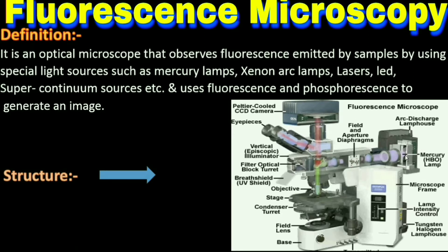The light source should be a mercury lamp or xenon arc lamp. Here we are using the mercury lamp. The light passes from here and reaches this filter. After the filter, it produces only monochromatic light, which then reaches the beam splitter — also called the dichroic mirror. The dichroic mirror splits the beams, and when it reaches the dichroic mirror, it diverts the light through the objective lens to reach the sample.